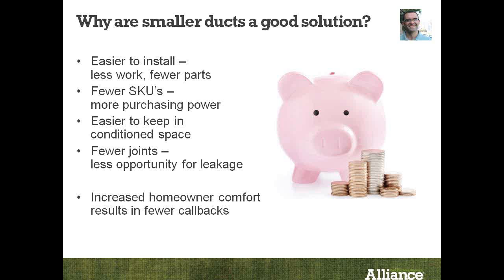Smaller ducts are much easier to put into conditioned space. This is important because most of the energy code is trending toward ducts in conditioned space. It's reducing the load on the house, and it's pretty much the right way of doing this. You have less risk in a hot, humid climate like the South, again, Houston, where if you have air conditioning ducts in your attic and there's air blowing in from the outside, you could have condensation onto your ducts if they're not well insulated.